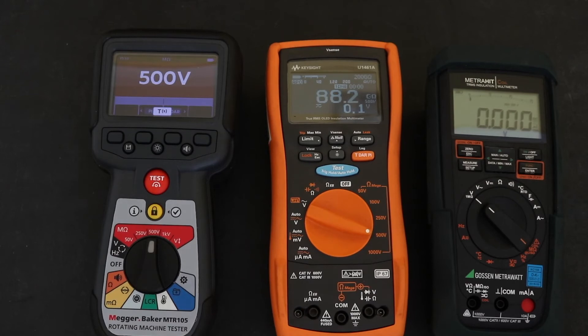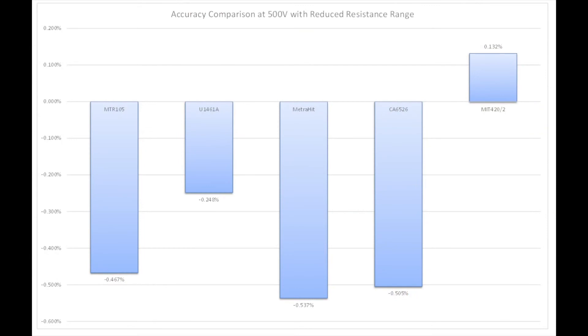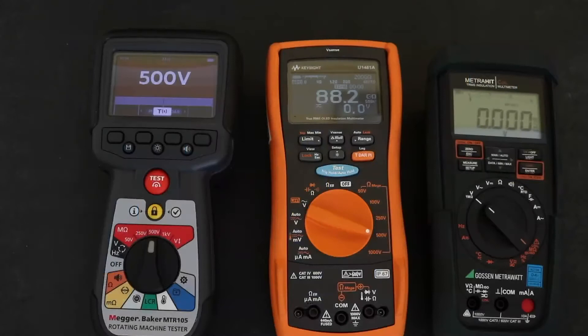So to include the Metrahit coil into the equation, what I actually do is reduce the test range down to the 3 giga ohm that the Metrahit can test up to. You can see here all I've done is given the overall accuracy comparison across this reduced test range. You can see actually the MTR105, much more accurate down at the bottom end, is more accurate than the Metrahit unit and the Chauvin Arnoux unit, not as accurate as the Keysight unit at 0.248%, but the MIT 420 again comes out on top, is more accurate than all four of these units and is actually the cheaper tester of the bunch as well.